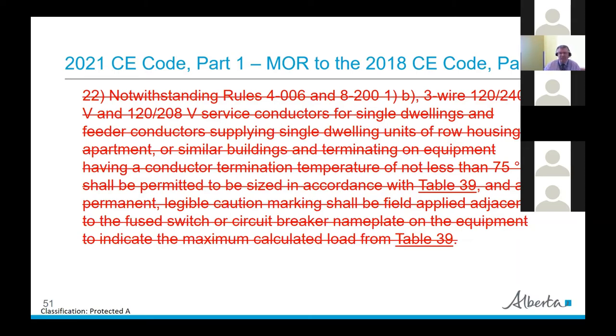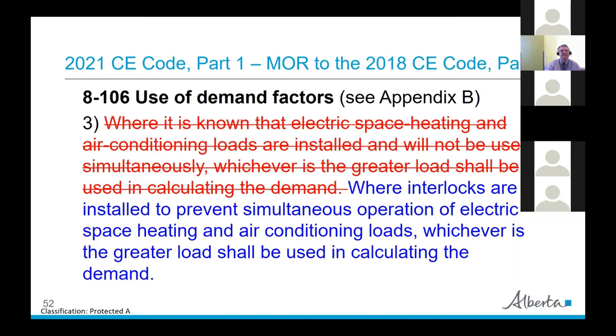Here's another eyebrow-raiser. We've always had the rule that where electric space heating and air conditioning loads are installed and will not be used simultaneously, whichever is the greater load shall be used in calculating the demand. The change is that it now says 'where interlocks are installed to prevent simultaneous operation of electric space heating and air conditioning loads.' Under the 2021 code, there will now have to be an electrical interlock rather than just depending on making sure it doesn't happen simultaneously.